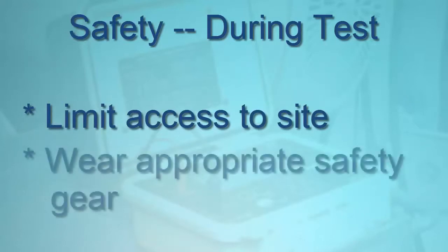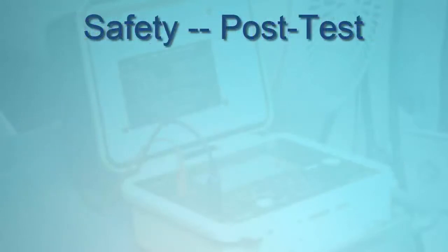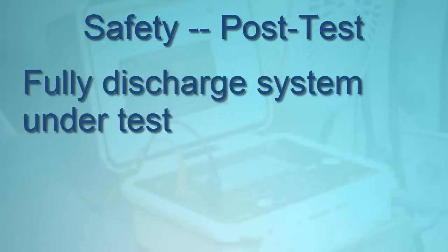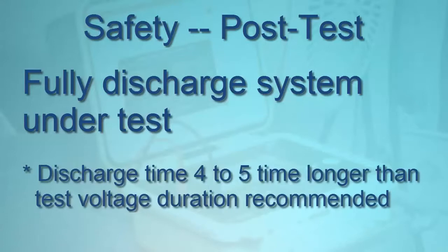Also, be sure to use personal protective gear, such as gloves, where appropriate. And after the test is complete, make sure the system under test is fully discharged. A minimum discharge time of 4 to 5 times the duration of the applied test voltage is recommended. Some insulation resistance test instruments feature a built-in circuit to ensure a safe discharge after the test, ensuring devices are safely discharged after every test.